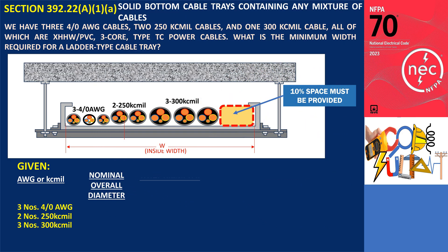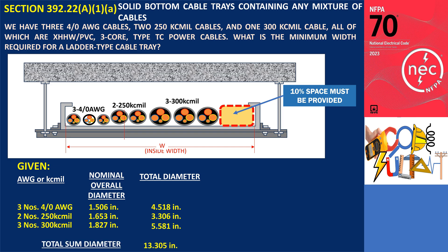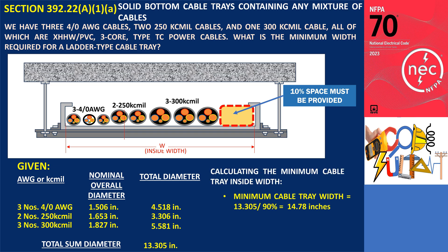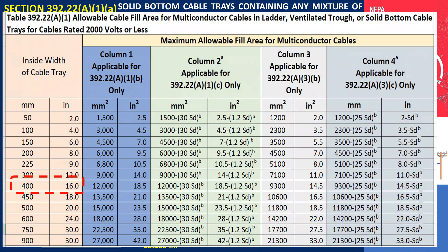The first step is to determine the nominal diameter of each cable, which can be found in the catalog data. The nominal diameter for the 4-aught AWG cable is 1.506 inches; since there are three of these cables, their total diameter is 4.518 inches. For the two 250 kcmil cables, the nominal diameter is 1.653 inches, giving a total diameter of 3.306 inches. The nominal diameter for the 300 kcmil cable is 1.827 inches, giving a total of 5.481 inches. Adding these together, the total diameter of all the cables is 13.305 inches.